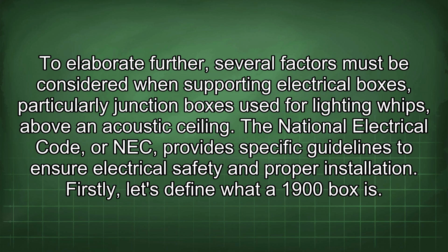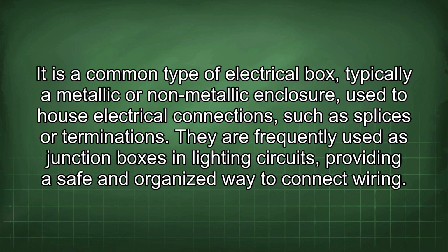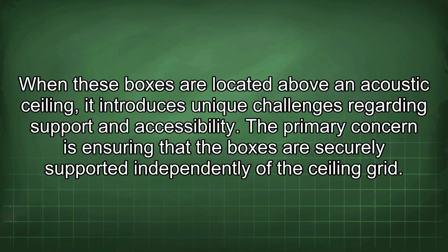To elaborate further, several factors must be considered when supporting electrical boxes, particularly junction boxes used for lighting whips, above an acoustic ceiling. The National Electrical Code, or NEC, provides specific guidelines to ensure electrical safety and proper installation. Firstly, let's define what a 1900 box is. It is a common type of electrical box, typically a metallic or non-metallic enclosure, used to house electrical connections such as splices or terminations. They are frequently used as junction boxes in lighting circuits, providing a safe and organized way to connect wiring. When these boxes are located above an acoustic ceiling, it introduces unique challenges regarding support and accessibility.